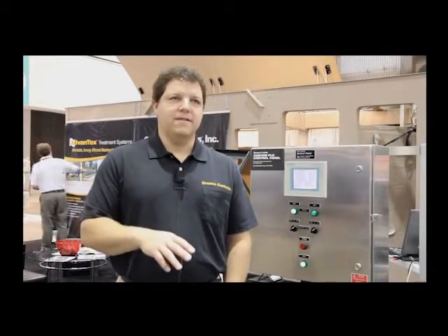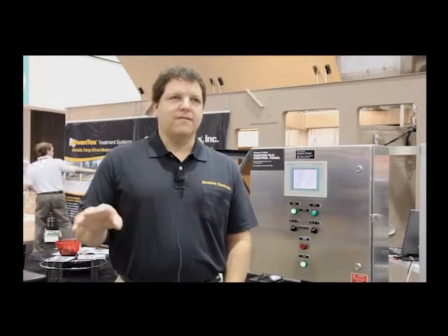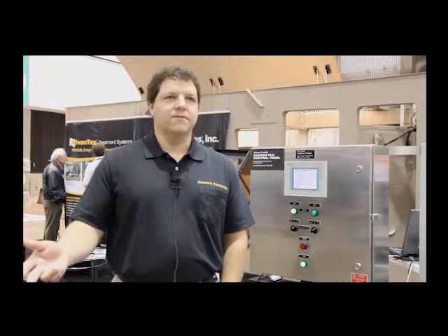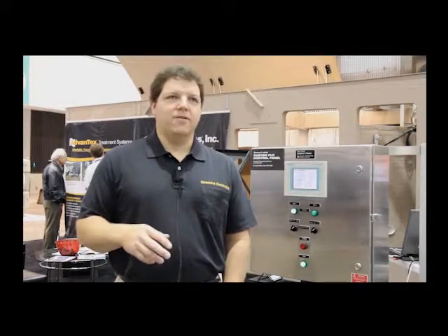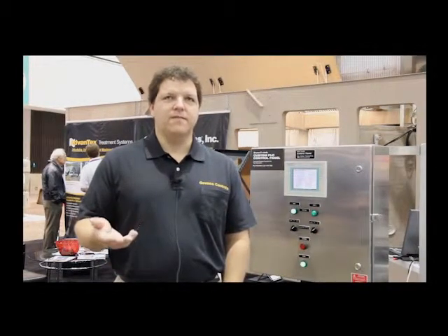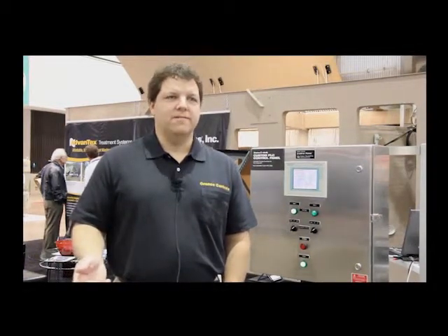We can start the pumps with many methods, anything from a simple IEC or NEMA rated starter up to a VFD or soft start. There's a lot of considerations that go into how you want to run the motor—do you want to run it full speed, or do you want to vary the speed? A lot of water systems vary the speed of the motor just to have constant pressure for a booster application. In wastewater, you may be varying the speed to keep the lift station at a set level, no matter how much flow is coming into it.